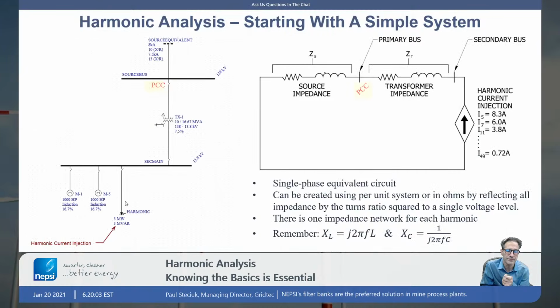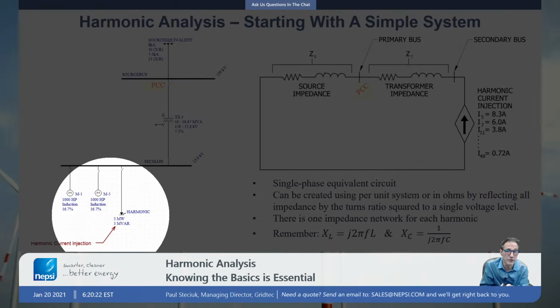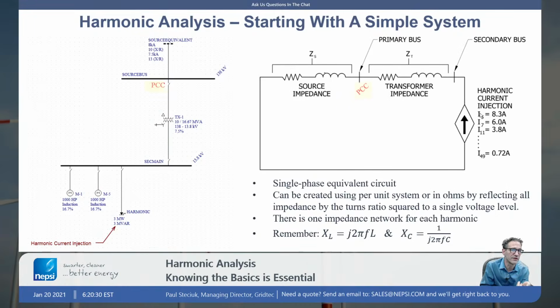At the end here we have the harmonic current injection. In general, nonlinear loads are often modeled as harmonic current injections, ideal current sources, and that's what you would typically see. What is the harmonic current injection from an LCI drive? It has a characteristic impedance, and you can take that value and put it into your analysis program at each and every frequency. Here we have assumed a value of I5, which means the fifth harmonic, and it's 8.3 amps. I7, 6 amps. I11, 3.8 amps.